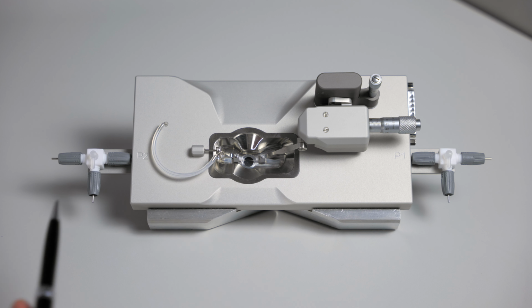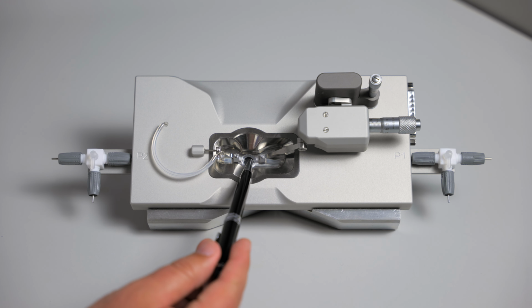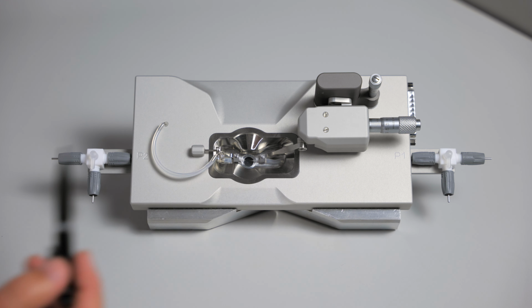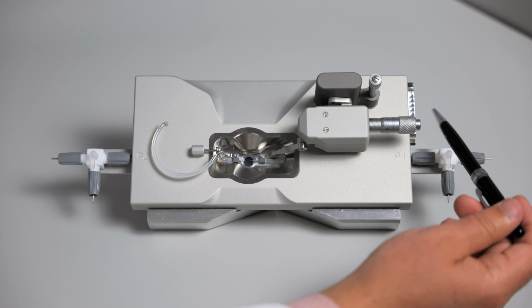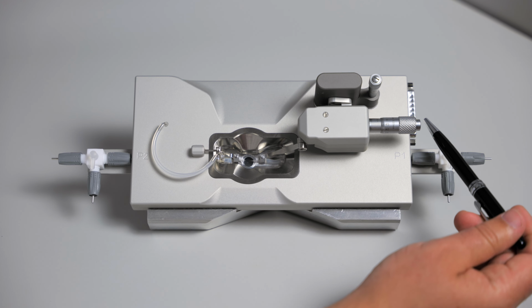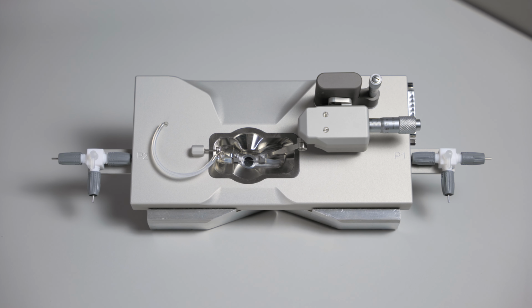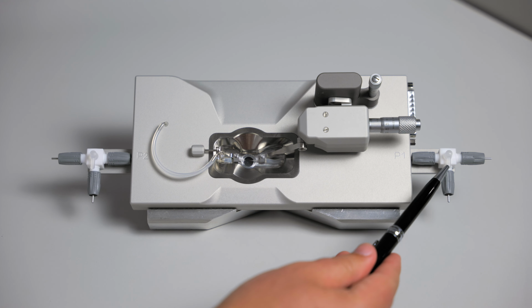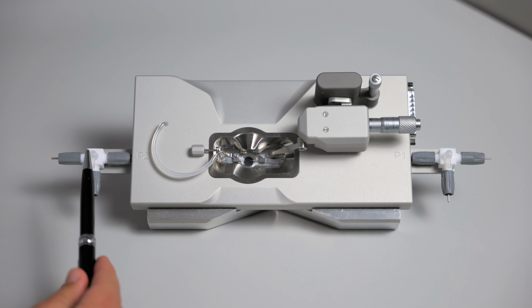The 114PN chamber will actually house the vessel that you have mounted between 2 glass cannulas or 2 stainless steel cannulas. Temperature and a heating unit are actually built into the chamber itself. This connection is for the Myograph cable that will be going to the interface. There are 2 three-way valves on either side of the chamber.